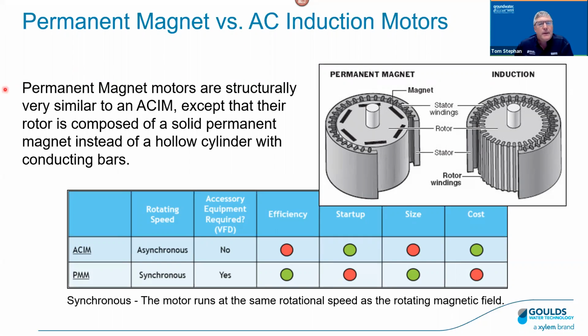So we can see here permanent magnet motors are structurally very similar to an AC induction motor, except that the rotor is comprised of a solid permanent magnet instead of a hollow cylinder with conducting bars. So we can see here in the picture, the rotor for the magnet, a solid permanent magnet, as opposed to the induction motor, which is a hollow cylinder with conducting bars. So again, today we're going to really focus on the induction motor, but I think it is important to understand the basic differences between the AC induction motor and the permanent magnet motor.